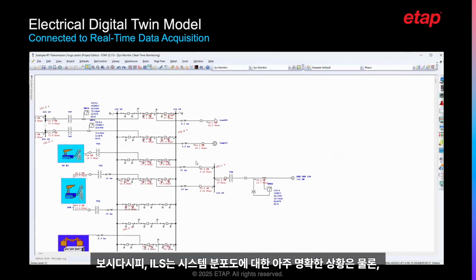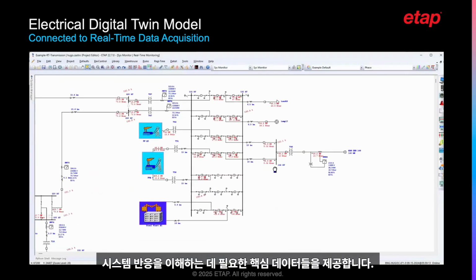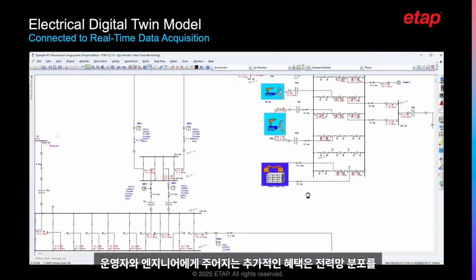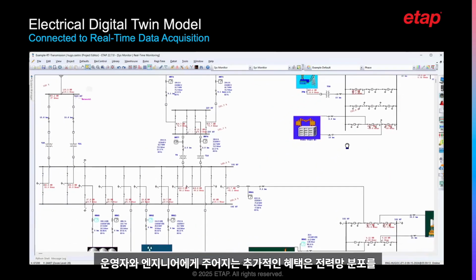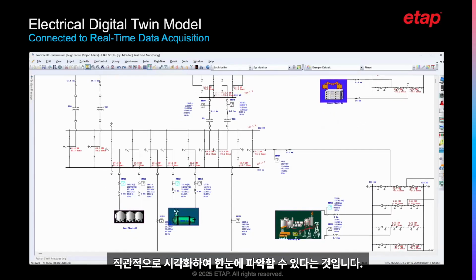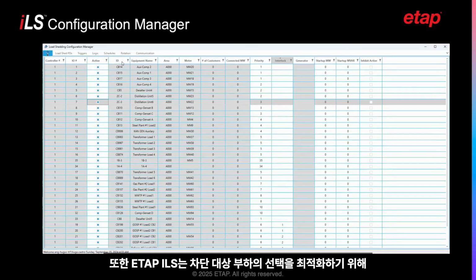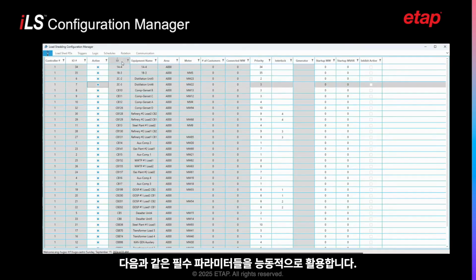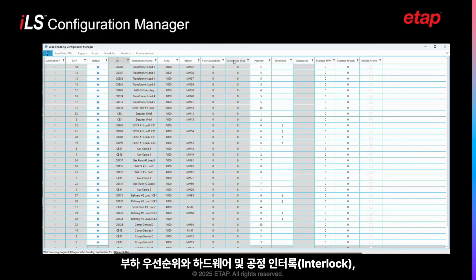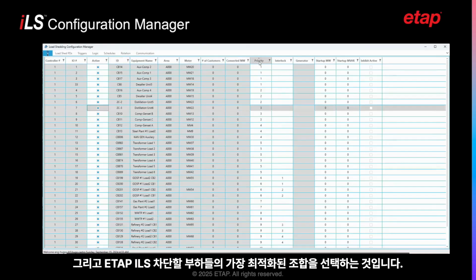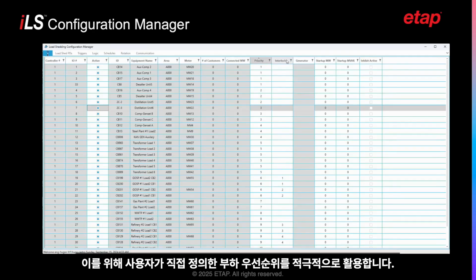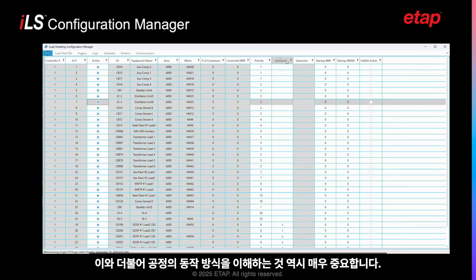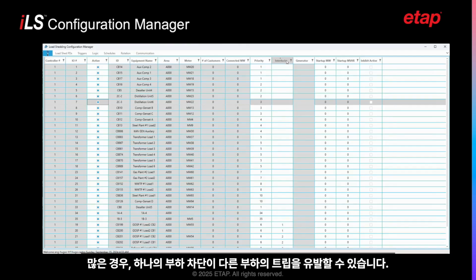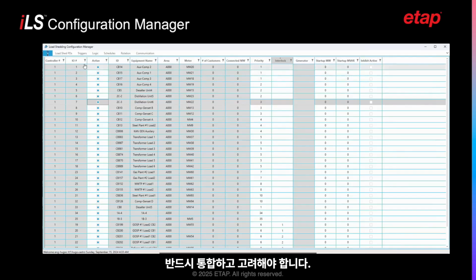As you can see, it provides a clear picture of the system distribution as well as the data required to understand system response. An added benefit for operators and engineers is that they are able to visualize the network distribution. In addition, ETAP ILS utilizes the following parameters to optimize the loads to shed selection: load priorities, hardware and process interlocks, and selection of the best combination of loads to shed. It utilizes user-defined load priorities. In addition, it is important to understand process behavior. In many cases, dropping one load can cause other loads to trip. Hardware and process interlocks must be incorporated and considered.